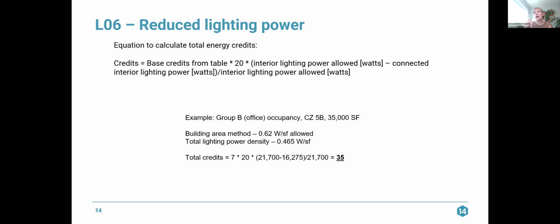So I did, for example, an office in climate zone 5B. It's 35,000 square feet. For simplicity, I'm just assuming we're going with the building area method. So there's 0.62 watts per square foot allowed. I said that we have a designed lighting power density of 0.465 watts per square foot. So we're going to take the base credits, which is 7, multiply it by 20, and then multiply that by our percentage savings, which is 25%, and we get 35 credits.